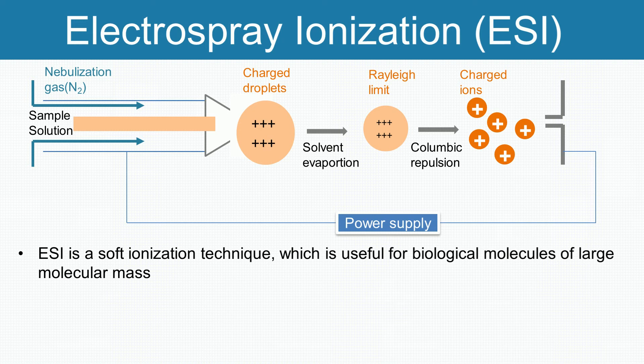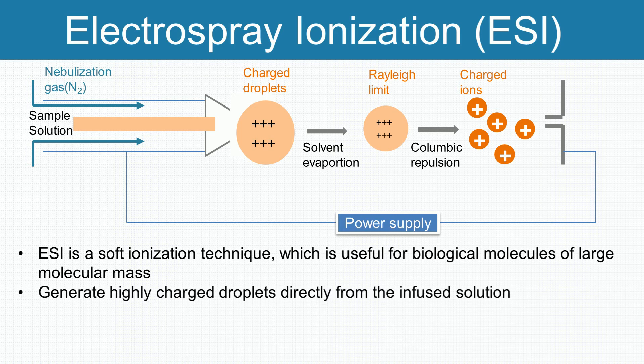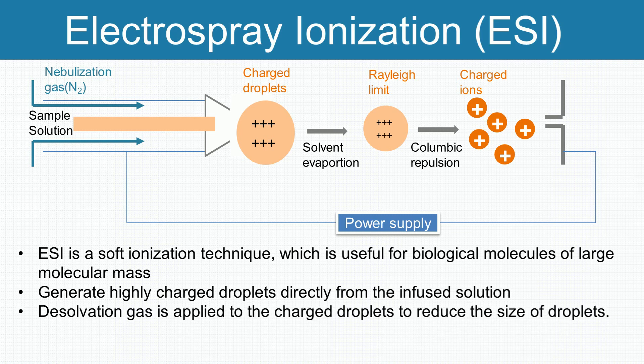Electrospray ionization uses an electrical stress between the probe exit and the counter electrode. The process results in the generation of highly charged droplets directly from the infused solution. With the help of another stream of heat or dry gas, which is called desolvation gas, the charged droplets are continuously reduced in size by evaporation of the solvent, leading to an increase of surface charge density and the decrease of the droplet radius.